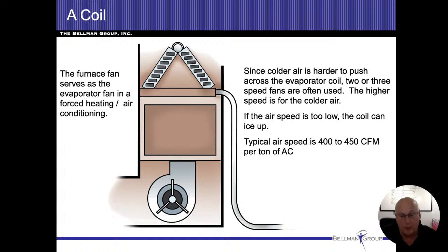So as you're checking your airflow, and this is a lot of problems you're going to run into, even with new construction homes, people end up undersizing ductwork. It may be correct in the math, but it just doesn't work, all right? So when you're going around and you've got the air conditioning running, try to hit every single room and make sure you've got a decent airflow coming out of there.